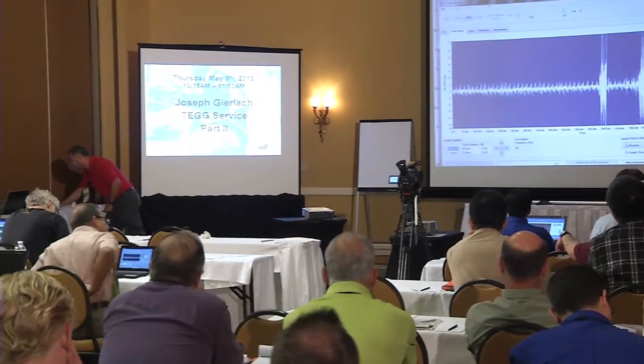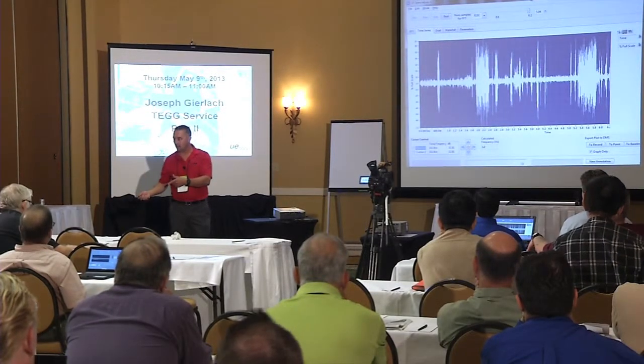If I look at the entire view, all 6 seconds, we can clearly illustrate, rescale that so I'm not chopping waveforms here. There we go. We can communicate or visualize, here's where it's quiet, and here's where it discharges. It's quiet here, and then we have a longer discharge, then more frequent discharges out here, then another period of silence, and that large, prolonged discharge at the end of the event. This view is dramatically different than what the tracking looked like, agreed?